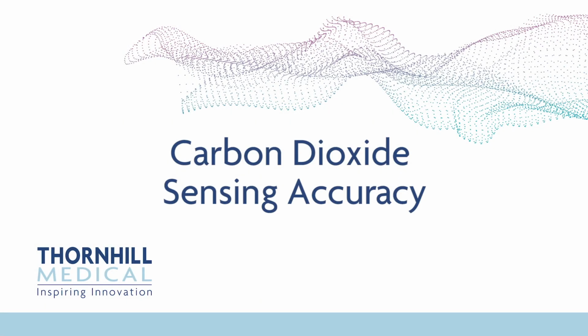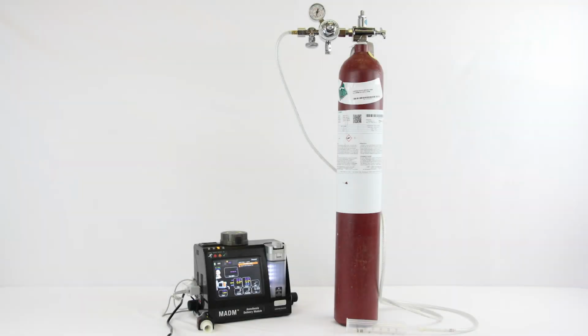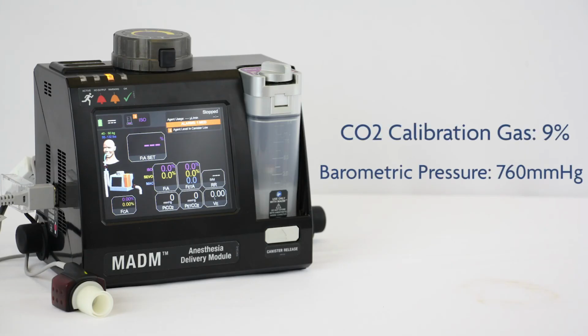Carbon dioxide sensing accuracy. To test the accuracy of the carbon dioxide or CO2 sensing of the mouth sensor of the MADM device, first locate CO2 calibration gas, which should have a CO2 concentration between 0 and 10%. In this example, we will be using calibration gas with 9% CO2.